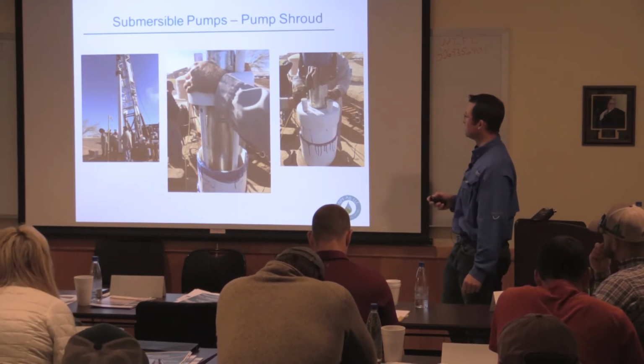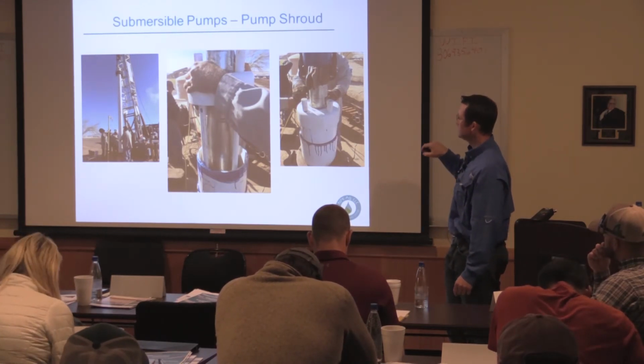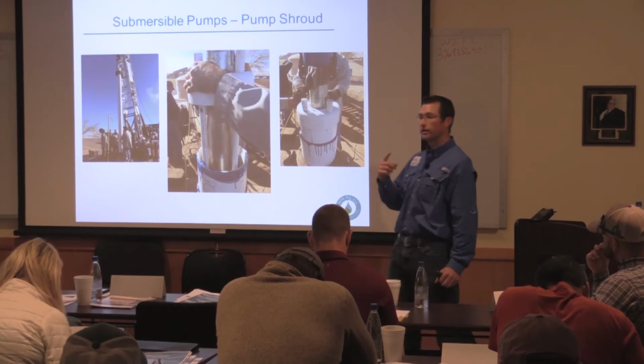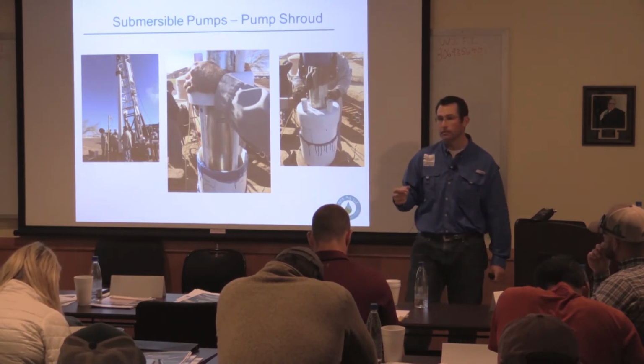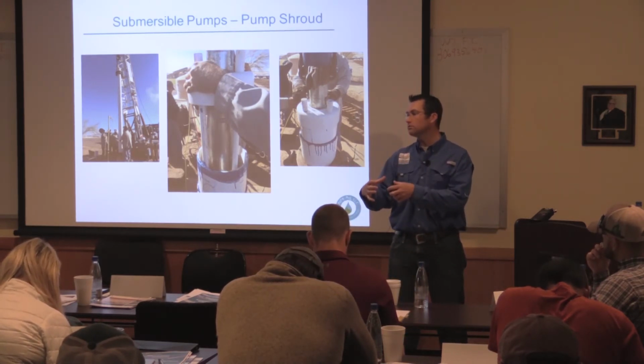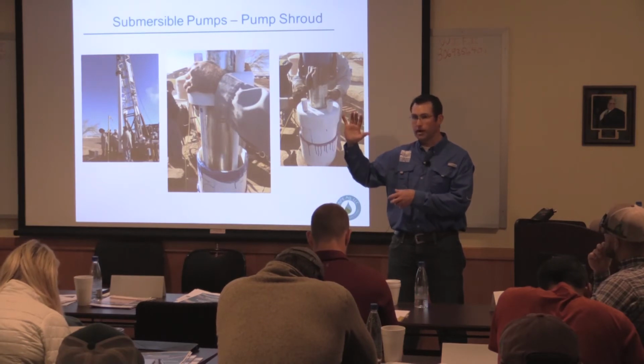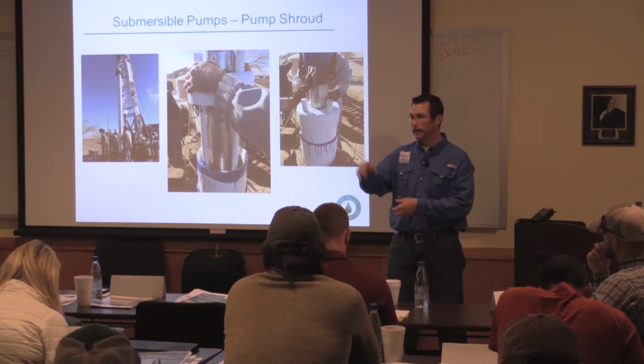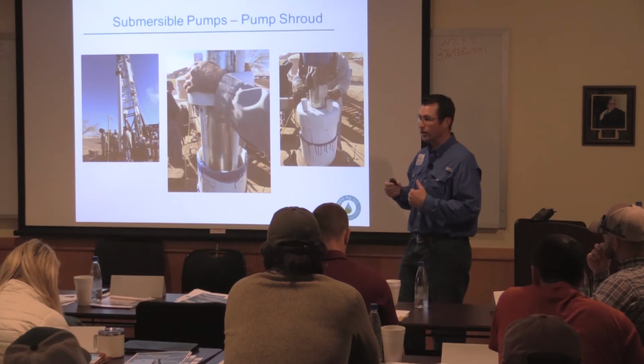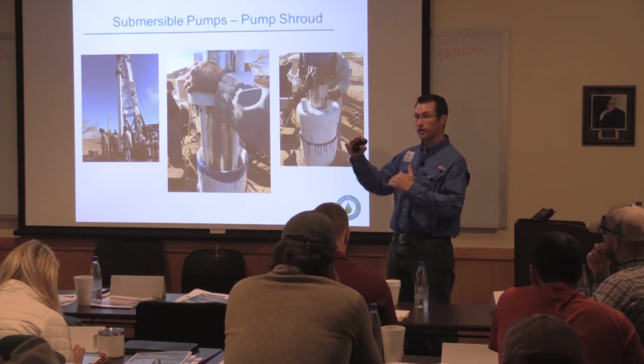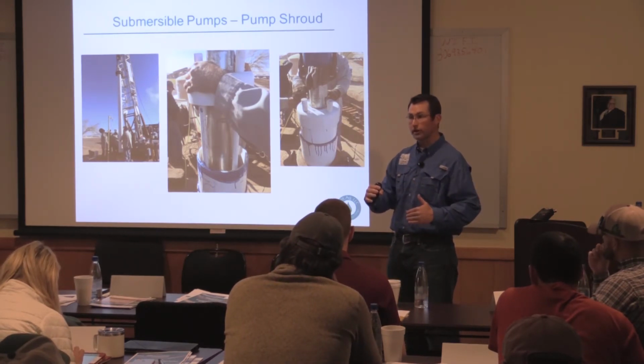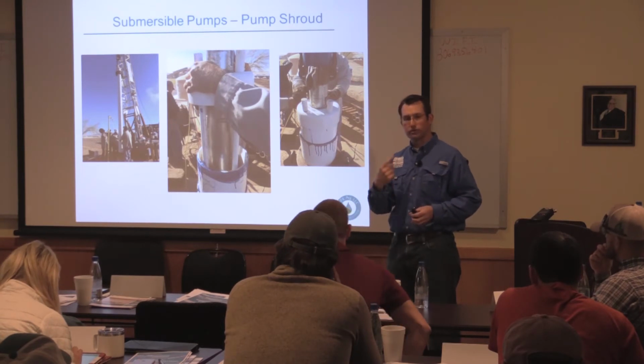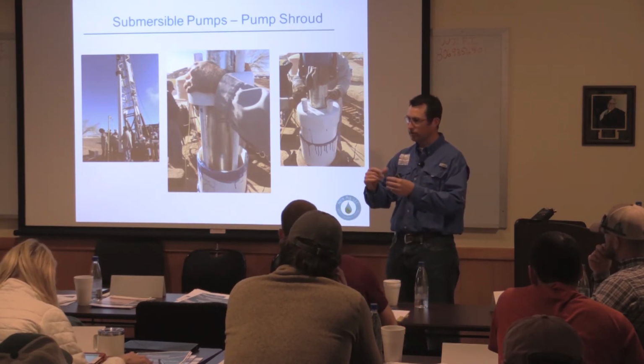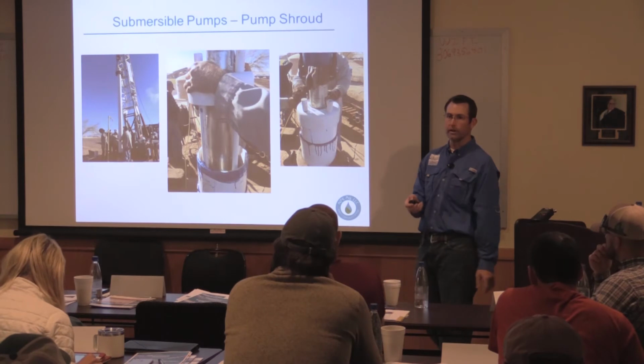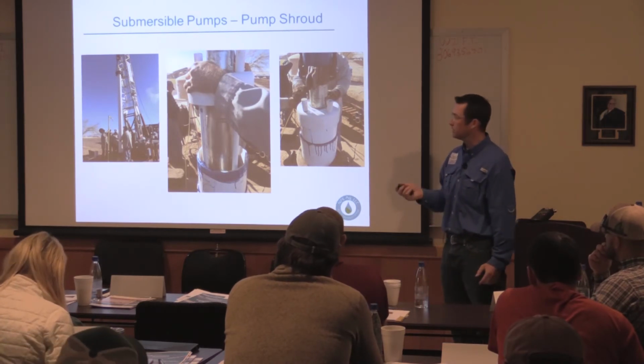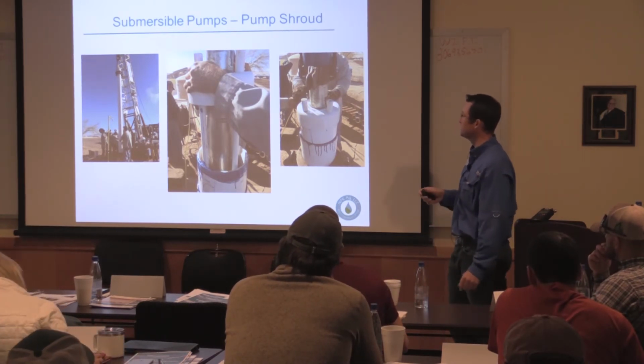Another point on these submersibles that's quite important is when you start to run them on a drive and you're slowing them down, it's good practice anyway to start looking at pump shrouds. Okay, is anybody familiar with pump shroud on the sub? It's almost mandatory in water above, say, 75 degrees. Here with Ogallala water, where it's a lot cooler, you can get away from it. But as you start slowing the motor down, you want to size the shroud down that you're forcing water through to cool it. Heat becomes your biggest contributor on killing submersible motors.